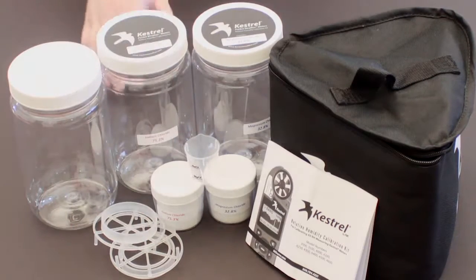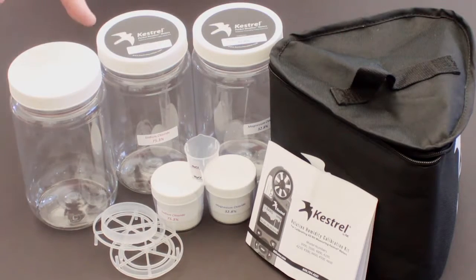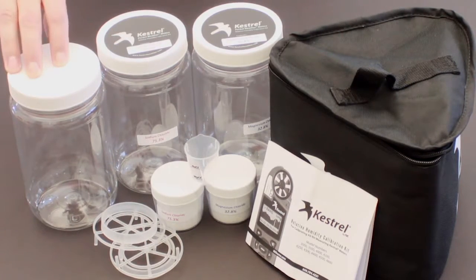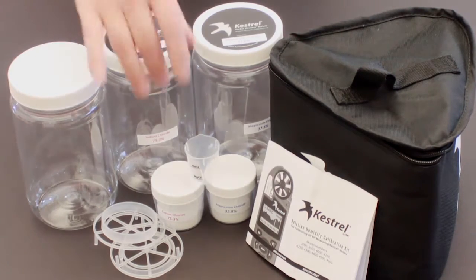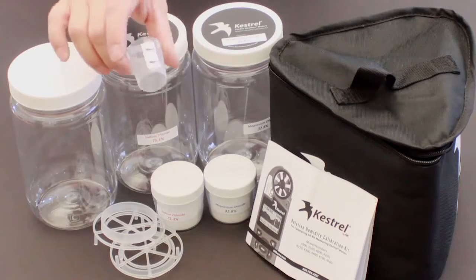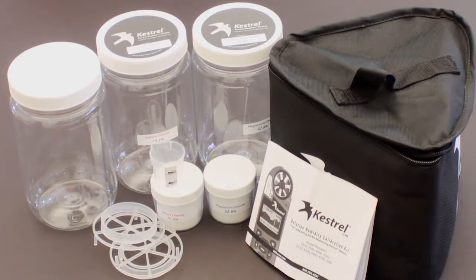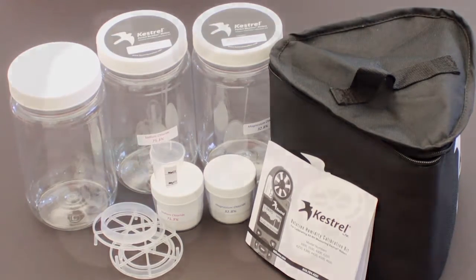Both come with grids that you will put in the jar, and one jar that will be filled with tap water to stabilize the temperature. Everything is color-coded to make things easier. And finally, we have a measuring cup that will help us prepare these salts for the RH calibration.